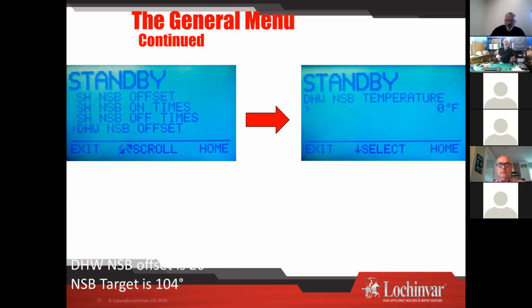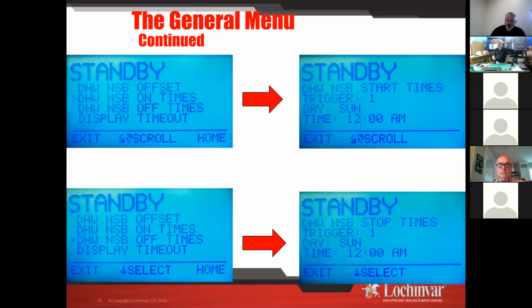What that does is it prevents the boiler from that little short cycling of turning on. It comes back on in the morning and runs the tank up to temperature. But what I've done is I've held it back enough that I put a bigger load on in the morning, as opposed to maybe firing once or twice in the night. It's just going to fire once in the morning, and it's going to take care of that. Think of doing this at a business that's closed for the weekend, and you can actually shut that down from Friday at 5 till Monday morning at 6 in the morning. You take a lot of cycles out of the boiler, and the cycling is important. It's big for efficiency as well.